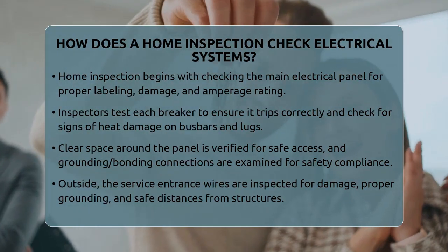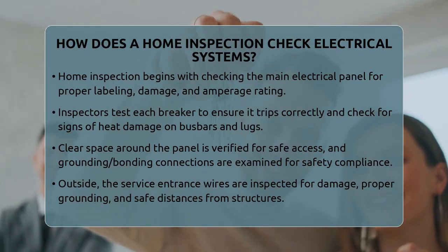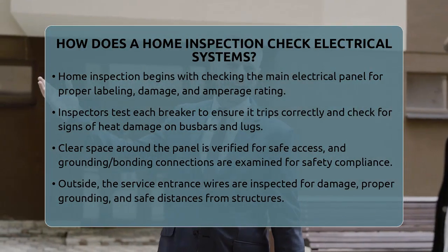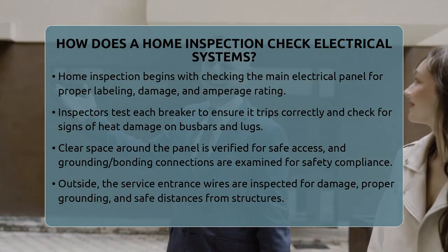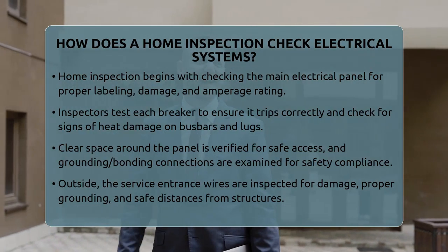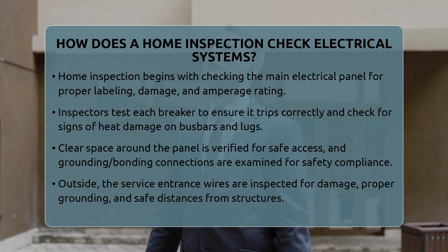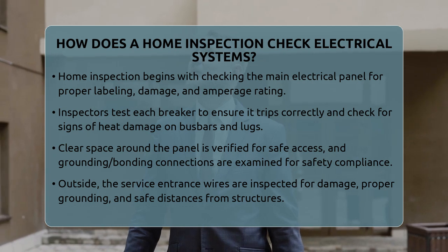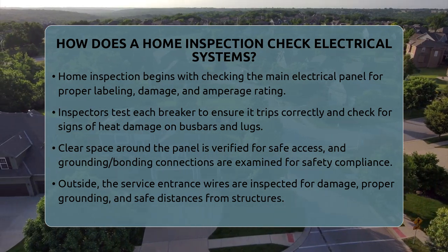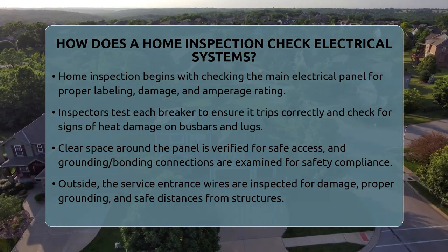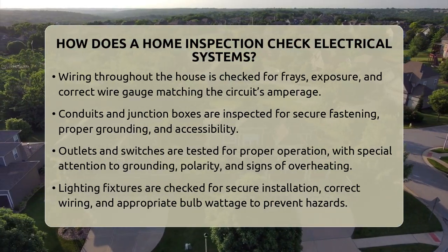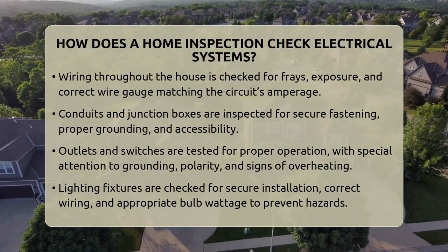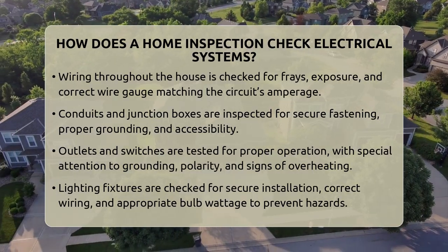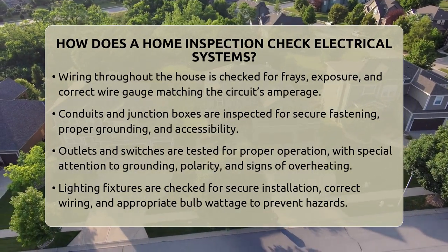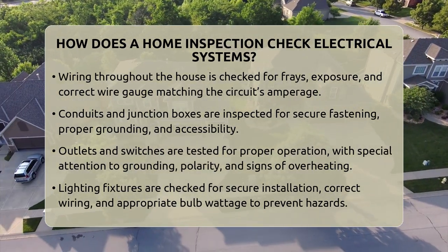Inside the panel, they also examine the busbars and lugs for signs of heat damage, indicating overloaded circuits or loose connections. Clear space around the panel is checked to ensure safe access for future work or emergencies. Grounding and bonding connections are carefully inspected to meet safety standards. If the panel hasn't been checked in over 5 years, it's especially wise to have it reviewed, since older panels might not support newer appliances or additional circuits.